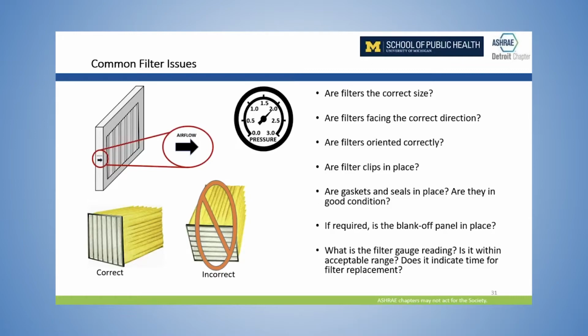And so some of the things here, I'm just going to briefly talk a little bit about the filter issues. Some of the things that I've seen in some of the assessments that I've done across the state in schools and in other buildings as well. You know, filters have a direction. If the maintenance tech doesn't understand this, they may install the filters backwards, and then you get reduced filter performance. The filters are designed for airflow through them in a particular direction. Again, one of the things that's usually broken in the facility is the filter gauge. So how do you know when you need to replace the filter? Are you replacing it on a schedule? Most cases not. So if you don't have that filter gauge to tell you when it's time to replace it, very often replacements happen much too late.